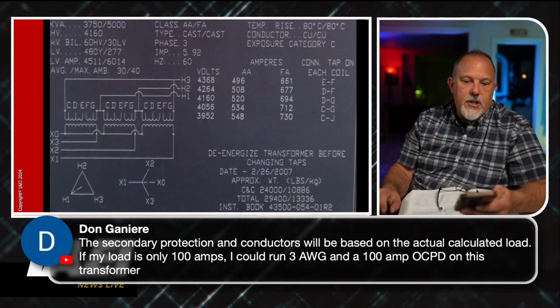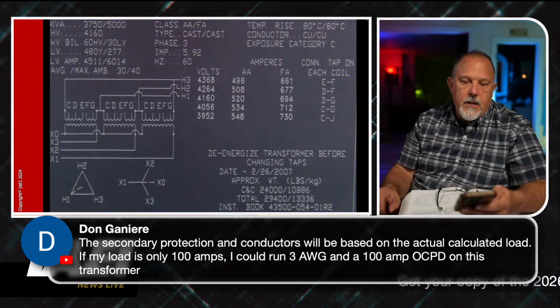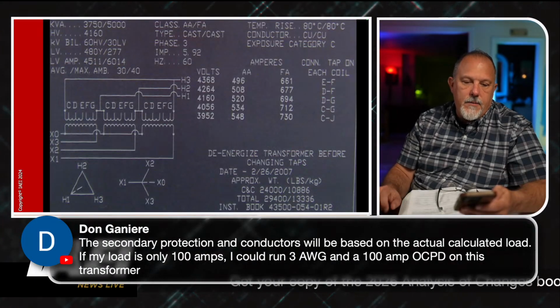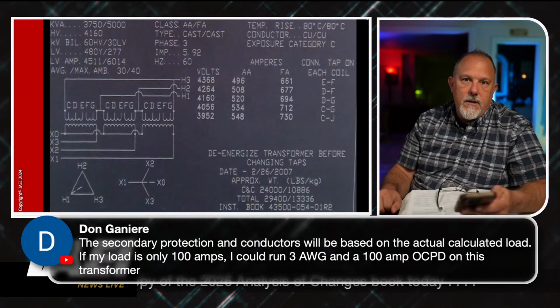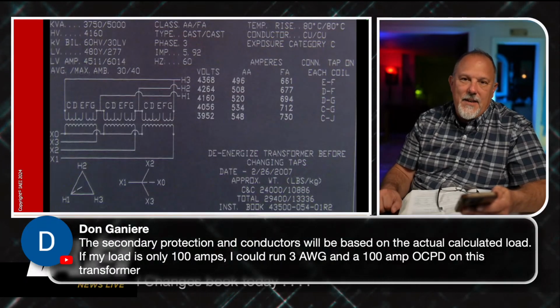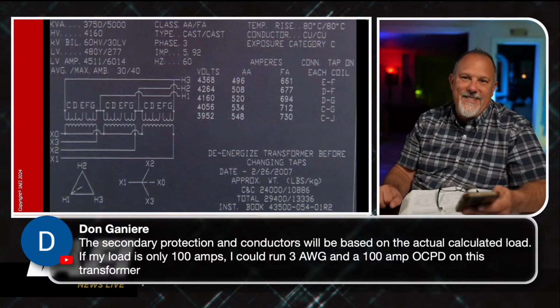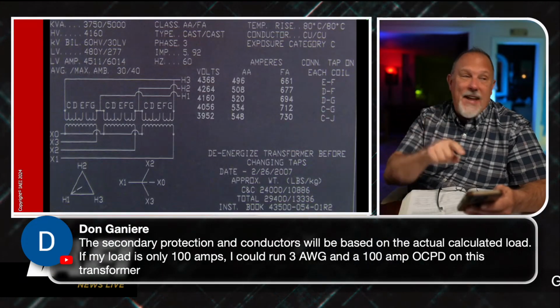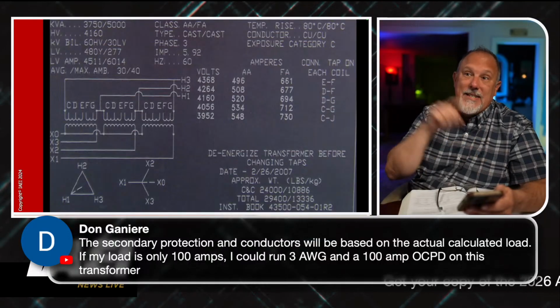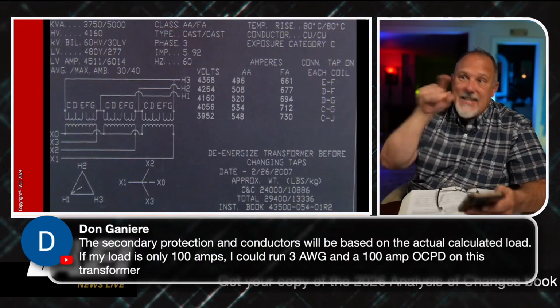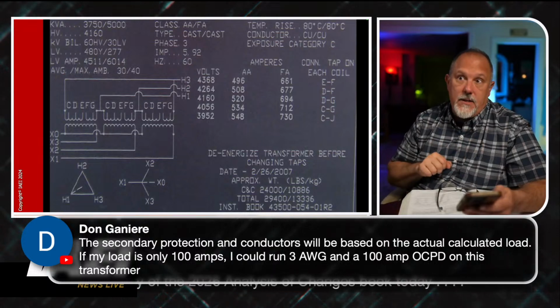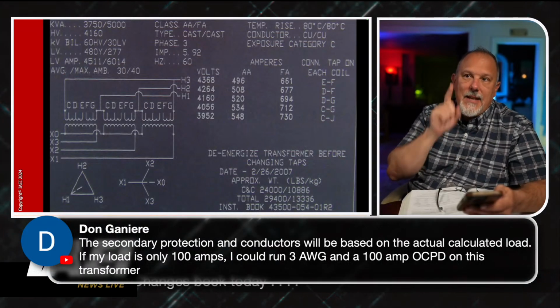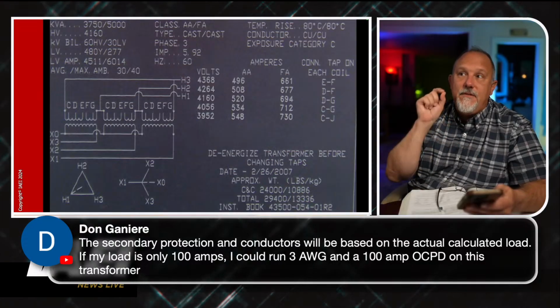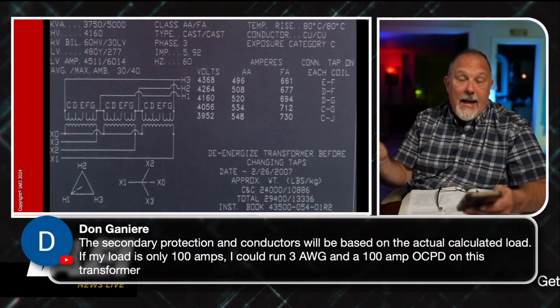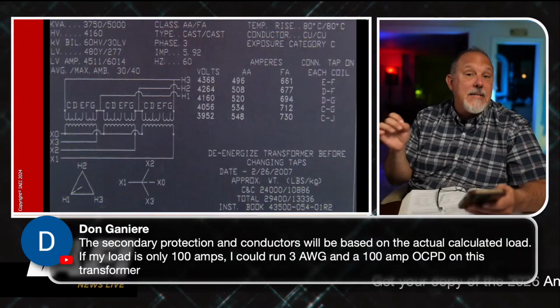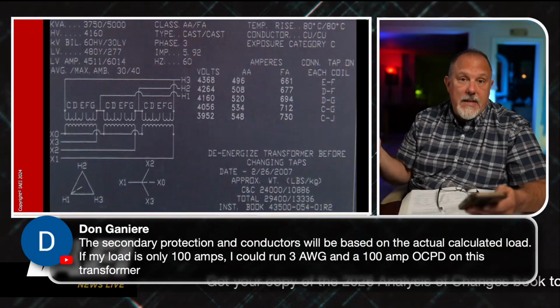Dawn says the secondary protection of conductors will be based on the actual calculated load. If my load is only 100 amps, well, yeah, of course. But you wouldn't be buying a 5,000 kVA transformer if your load was only 100 amps. And you would definitely not be adding fans to get more kVA if your load was less than the 6,000, because you wouldn't need to pay for those fans. So if my load was actually less than 4511, then why would you invest in a 5,000 kVA with fans? It just doesn't make sense. The financials don't make sense, Dawn.